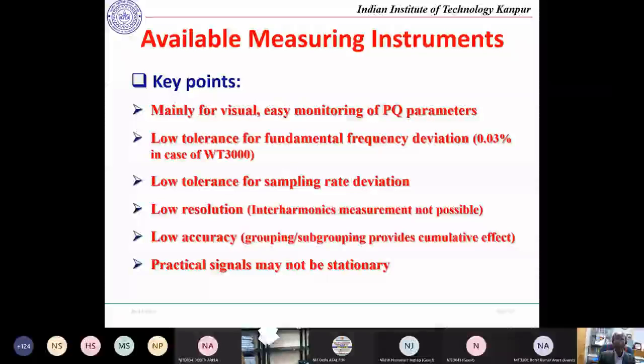It has a low tolerance of fundamental frequency deviation. For example, your device is set at 50 Hertz, and during operation the frequency changes. If the frequency changes too much, it will give wrong information. They only work correctly within about 0.03% deviation. A small deviation is okay, but if the deviations are sudden and wide, they will give you wrong information.